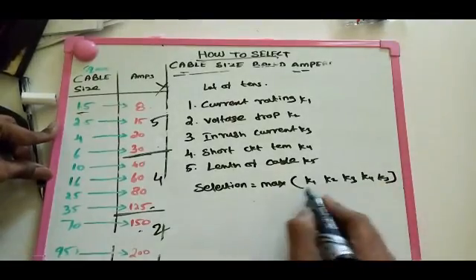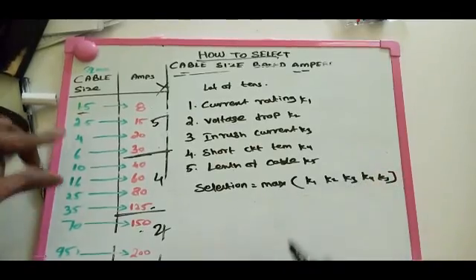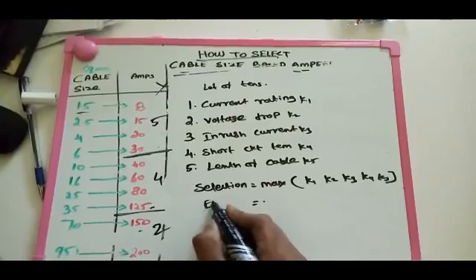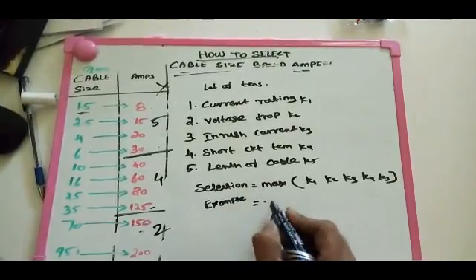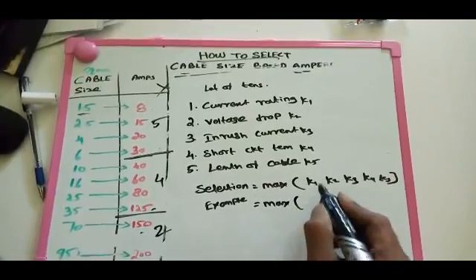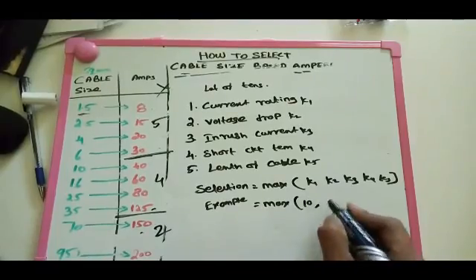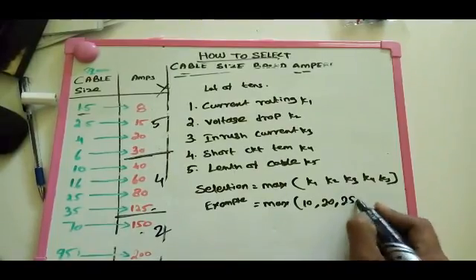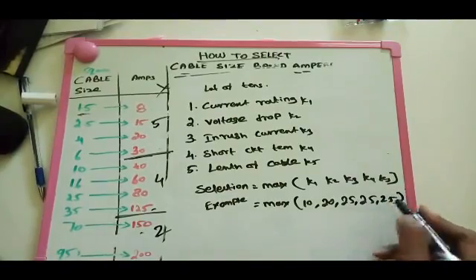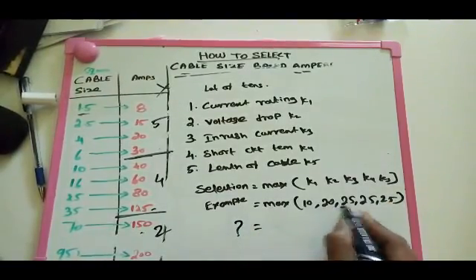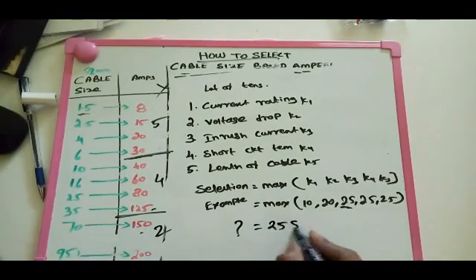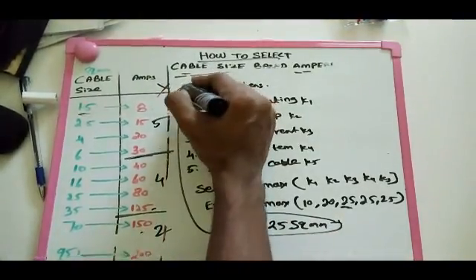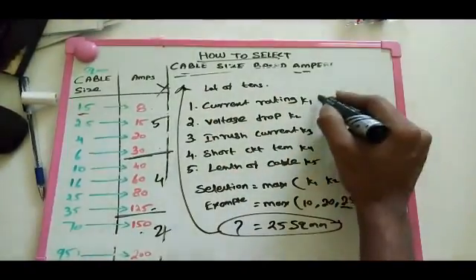After calculating K1, K2, K3, K4, and K5, whichever value is the maximum among these five is the one you use to select the final cable size. For example, if the values give cable sizes of 10, 20, 25, 25, and 25 square mm respectively, then the final correct cable size to select is 25 square mm — the maximum value among all factors.